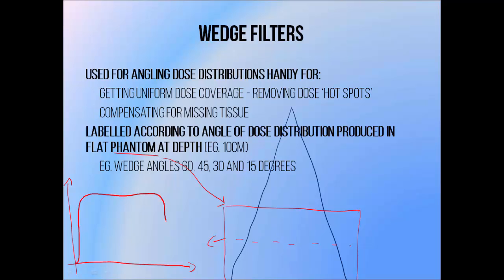Sometimes it's to our advantage to use a wedge filter to reduce the intensity of a beam across its axis. Putting a wedge-shaped filter in the beam means that different parts of the beam have to pass through different thicknesses of material before reaching the patient, and are attenuated to different degrees.